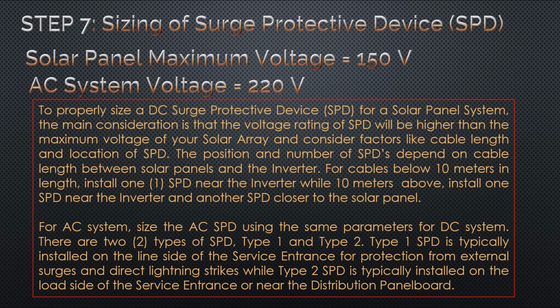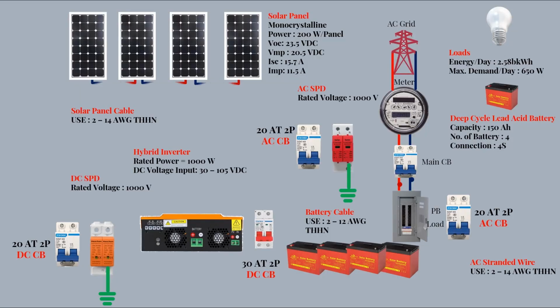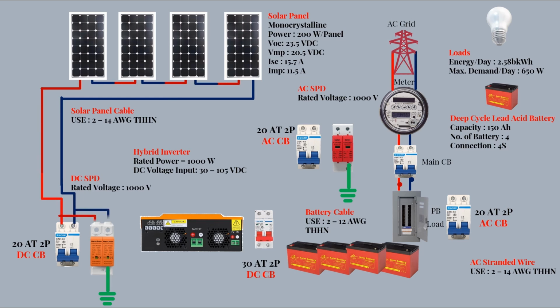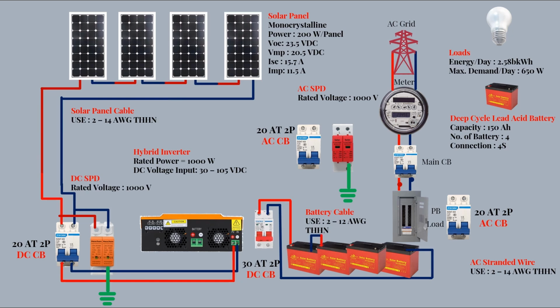There are two types of SPD, Type 1 and Type 2. Type 1 SPD is typically installed on the line side of the service entrance for protection from external surges and direct lightning strikes, while Type 2 SPD is typically installed on the load side of the service entrance or near the distribution panel board. So this is the summary of the hybrid solar PV setup. In this diagram, it is also indicated all the values of the parameters that are computed.